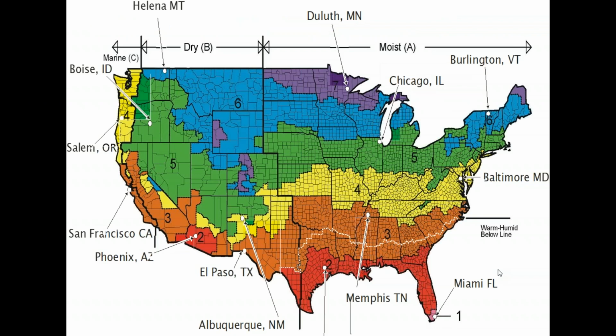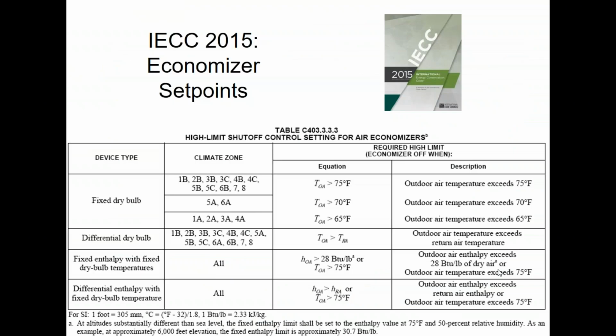For economizer set point requirements, we look at the climate zone map, and this is consistent amongst the ASHRAE and IECC standard. It does change in the future going forward, but it isn't different right now for the codes that our states are using. So if you guys are in Illinois, you're climate zone 5A, because you're to the right of the moist dry line. And for you guys in southern Wisconsin, you are 6A. Most of you guys are in Milwaukee area and Chicago area that are on this call. So 5A and 6A. The good news is those are both the same requirement from the economizer standpoint, so we can talk about them simultaneously.